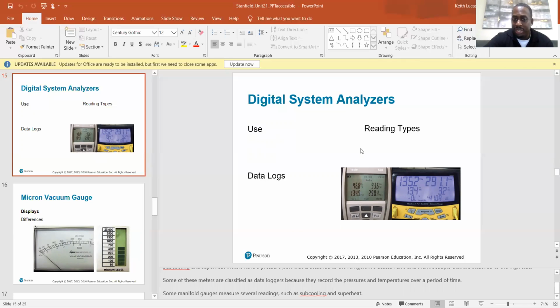I didn't have one of these. I did have one at a different company when I first got into the trade. I was working at C&L. They supplied all the trucks with superheat and subcool readers, and it was a whole separate tool. I had my mechanical gauges hooked up. Then I got this whole other tool, which is basically like a dual input thermometer, and you have to tape the thermocouple to the suction line and tape another one to the liquid line, and then it calculates your superheat and subcool. These do that.